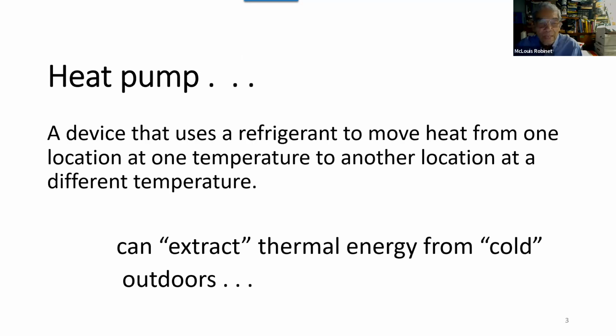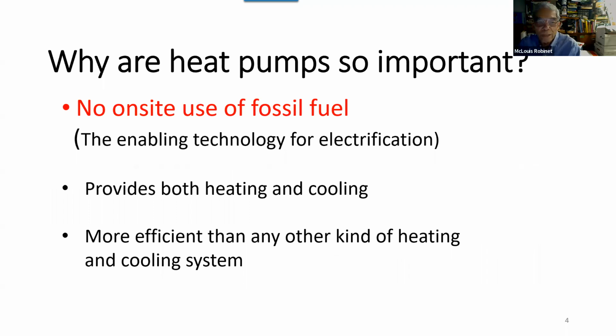A heat pump is a device that uses a refrigerant to move heat from one location at a given temperature to another location at a different temperature. That means we can extract heat from a cold place and dump it to another place to provide heat. So why are heat pumps so important? First is no on-site use of fossil fuels, and that is the enabling technology for electrification. Without heat pumps, we'd have a hard time justifying electrification. Second, it provides both heating and cooling, and it's more efficient than any other kind of system.